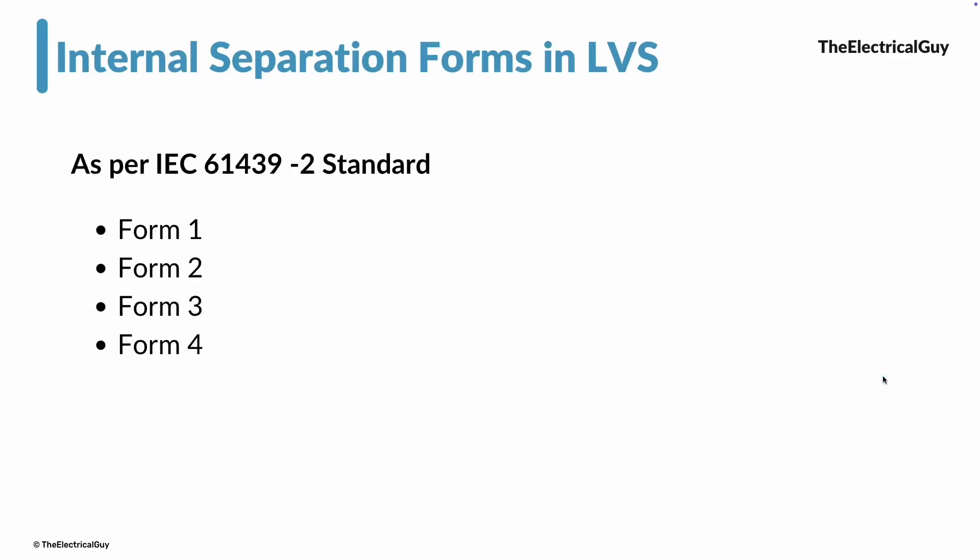The IEC standard has defined four major categories for separation forms: Form 1, Form 2, Form 3, and Form 4. Form 1 offers the least amount of safety and Form 4 offers the highest. The selection of form depends on where the low voltage switchgear is installed and its application. Where the highest safety is needed and downtime cannot be tolerated, Form 4 is the choice.